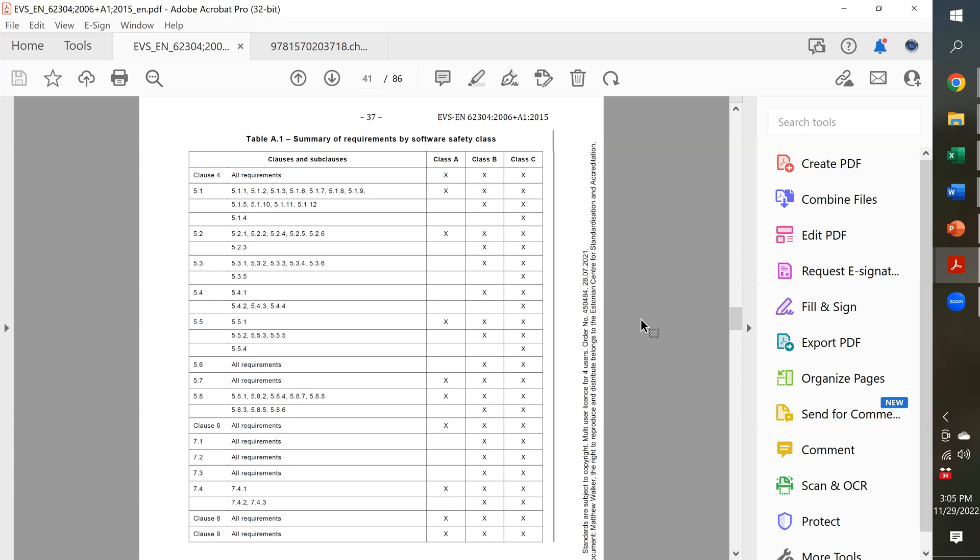So, anything pretty much that's getting CE marking review or it's going to be a 510K submission, it's probably going to be a Class B software. And you're probably going to have a moderate level of risk. There are a few that are minor level of risk, but that is not necessarily a Class A.